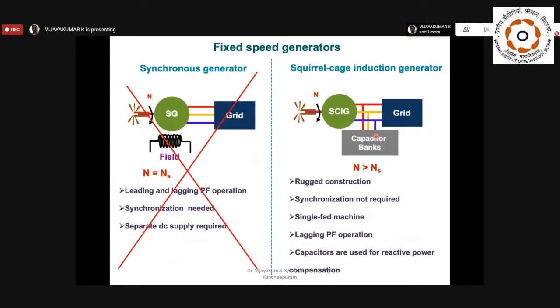Then the higher value gives a higher magnetizing current to the grid, so we are injecting reactive power into the grid. So it leads to leading power factor operation. That is not advisable from a power quality point of view, and it will give some kind of problem. So nowadays people are working on switched capacitor banks or STATCOMs and so on. You can take that as a research problem and work on it.